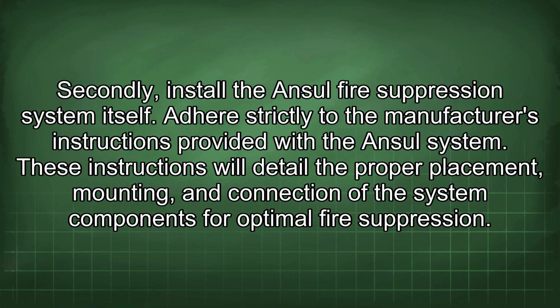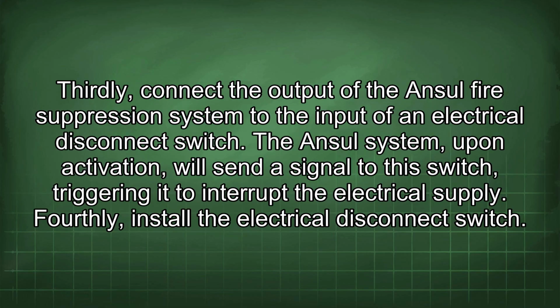Secondly, install the Ansul fire suppression system itself. Adhere strictly to the manufacturer's instructions provided with the Ansul system. These instructions will detail the proper placement, mounting, and connection of the system components for optimal fire suppression. Thirdly, connect the output of the Ansul fire suppression system to the input of an electrical disconnect switch. The Ansul system, upon activation, will send a signal to this switch, triggering it to interrupt the electrical supply.